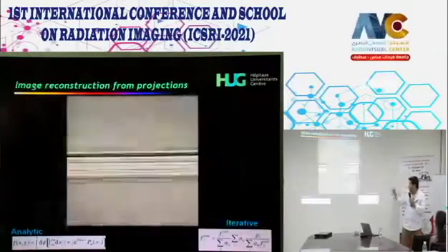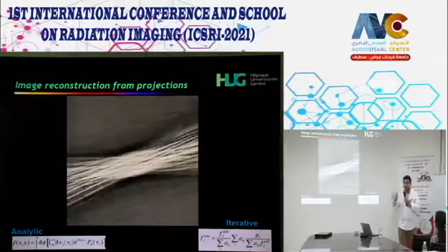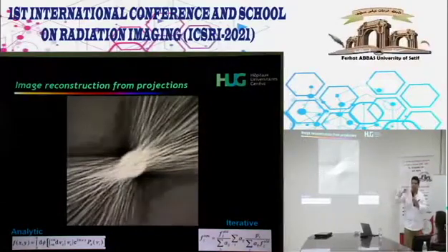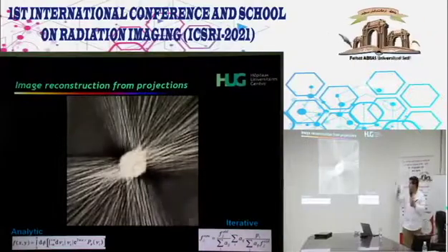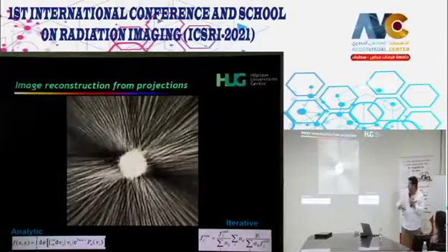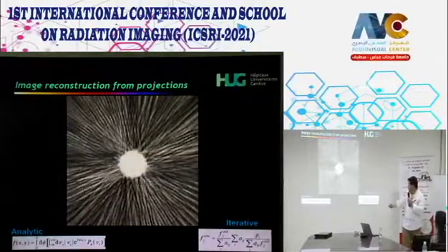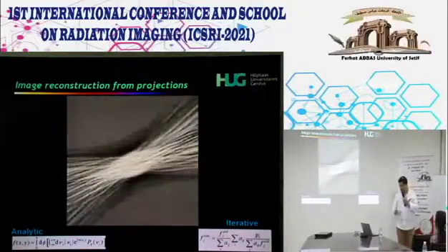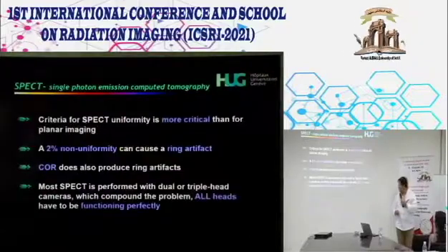And then we apply the same theory that I described before, either filtered back projection, which means filtering the projections in Fourier space and then back projecting them line of response by line of response to get the image, or one of the more advanced iterative reconstruction techniques that I'm going to touch upon later on.